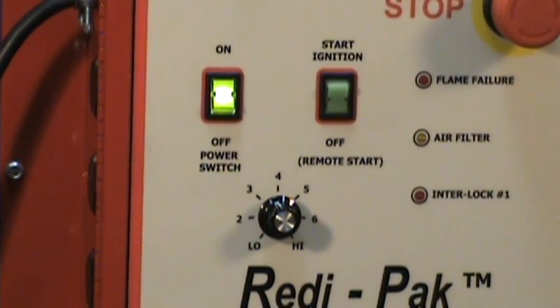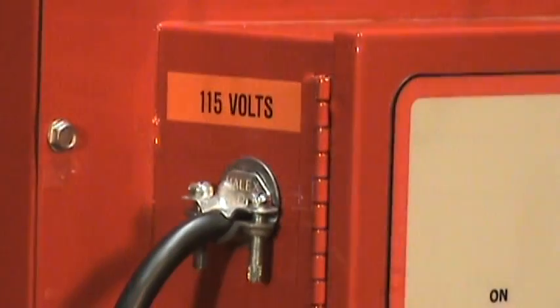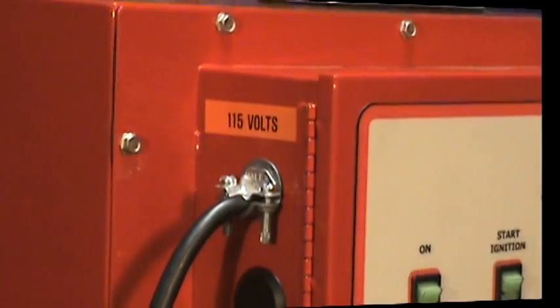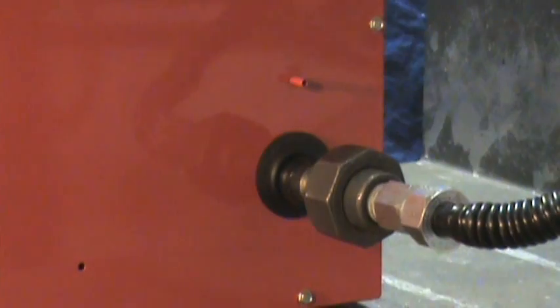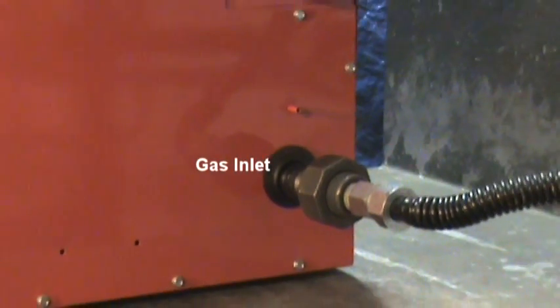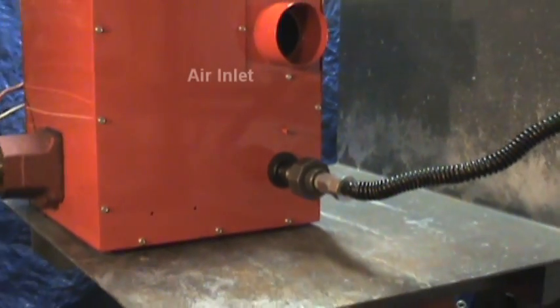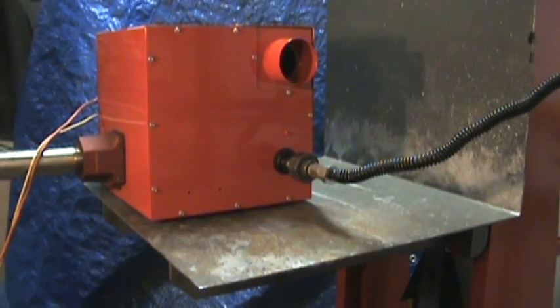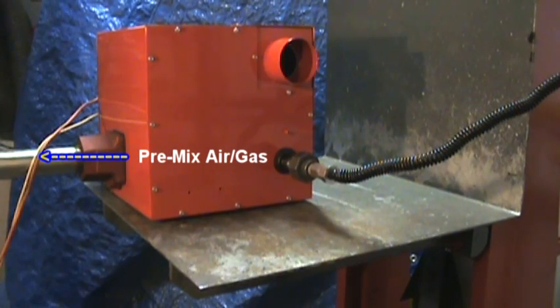We'll start by turning the power on. This starts the blower in the initial purge. The Redi-Pak operates on standard 115 volt AC electric power. On the reverse side of the unit, the gas inlet can accept either natural gas or propane. The air intake tube leads to the filter compartment. Upon ignition, the gas valves will open and the pre-mixed blower will supply the combustion mixture to the burner.